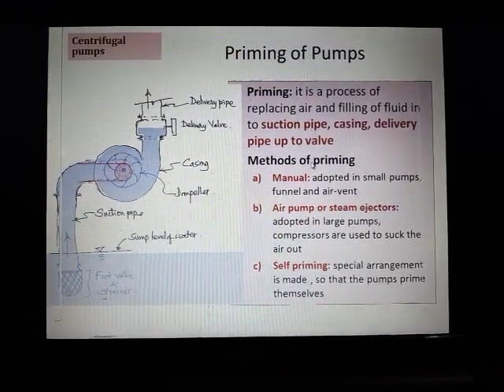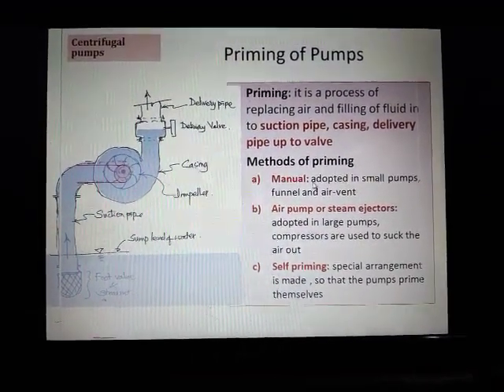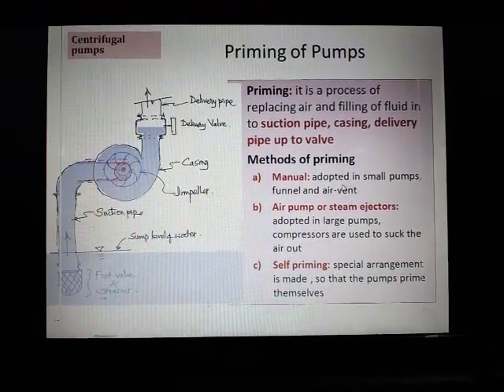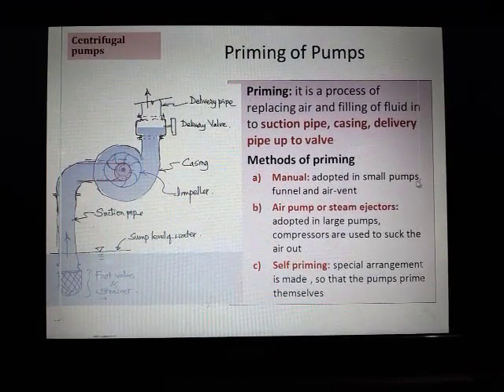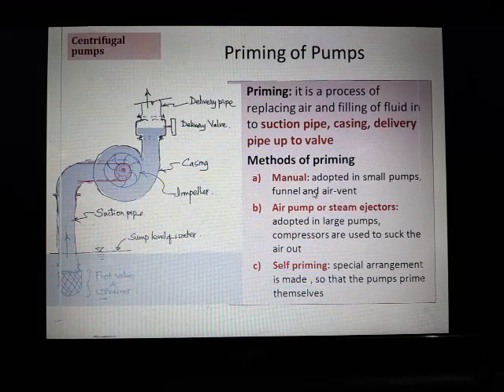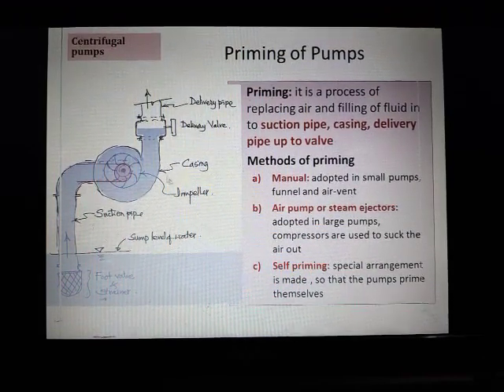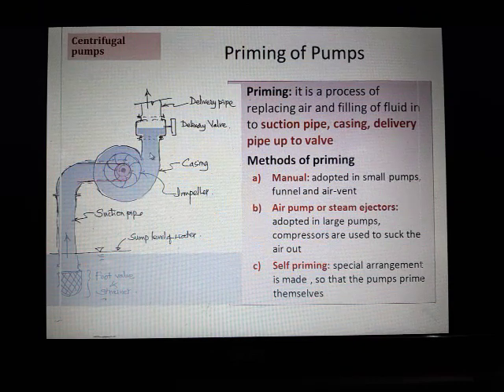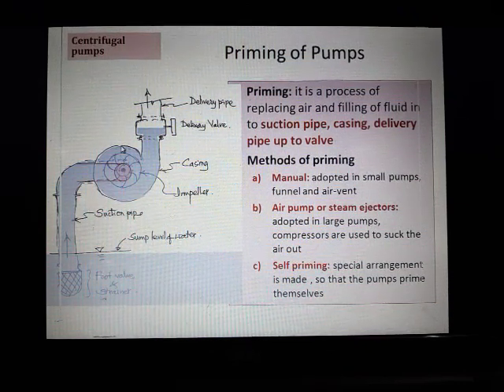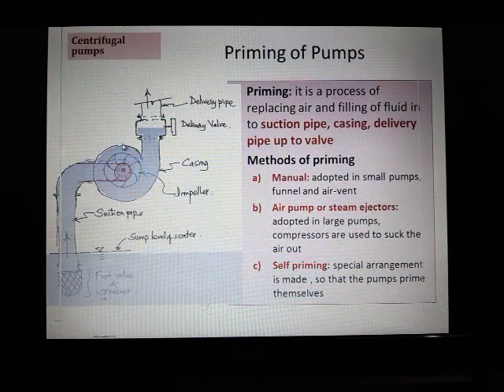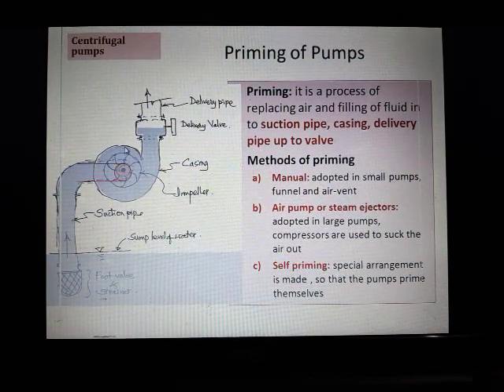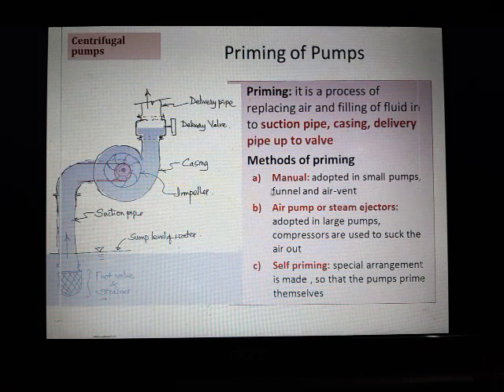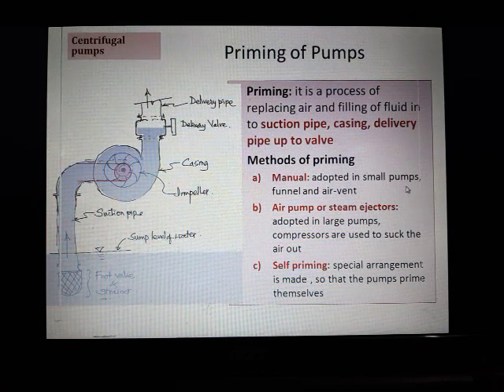Regarding methods of priming: there is manual priming, which is usually adopted in small pumps. A funnel is used and there is an air vent. There is a provision for putting water inside, and whatever air is present escapes out from a small vent which can be opened or closed. This method can be used only for smaller size pumps.